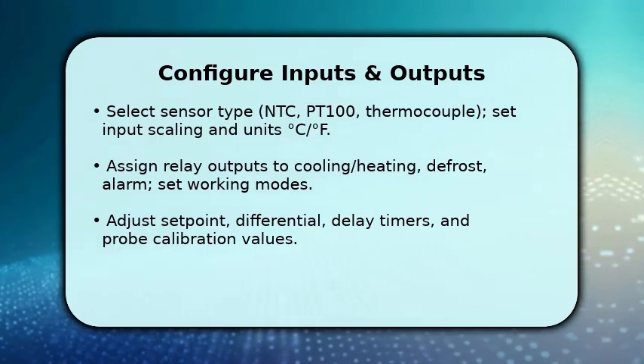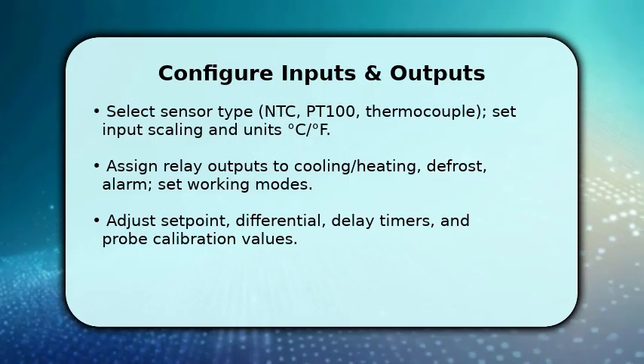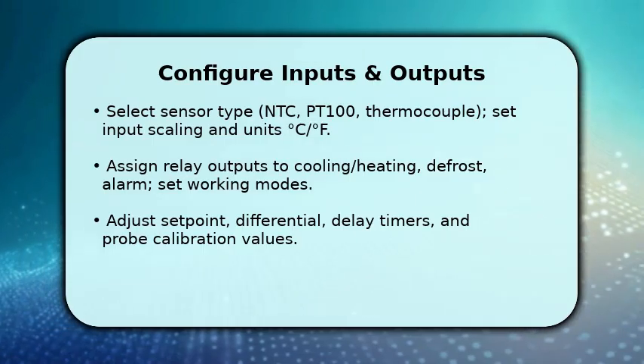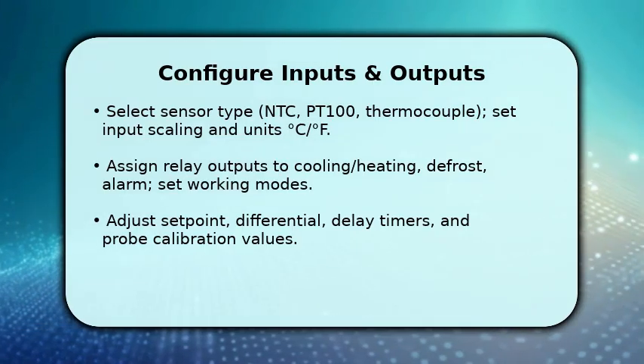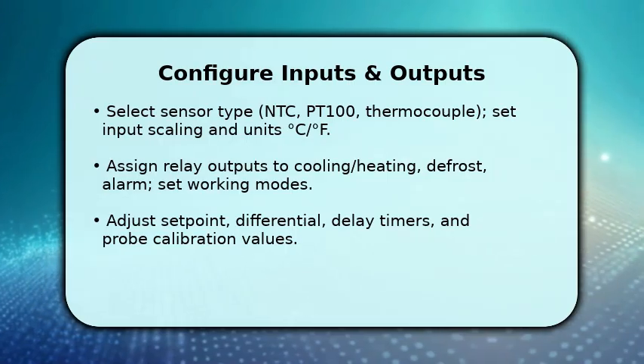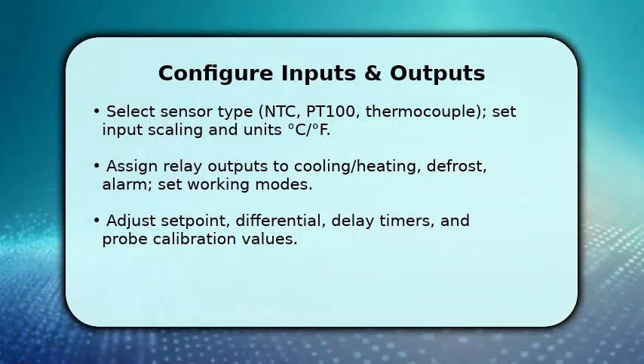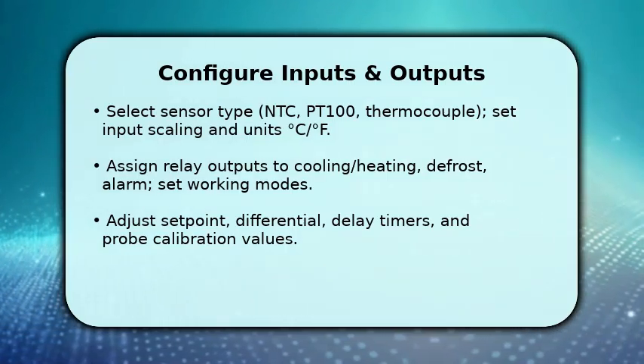Choose which relay controls cooling, heating, defrost, or alarm, and select their working modes. Then set your primary set point and differential hysteresis, and enter any required delay timers to prevent rapid cycling. Finally, perform a probe calibration.